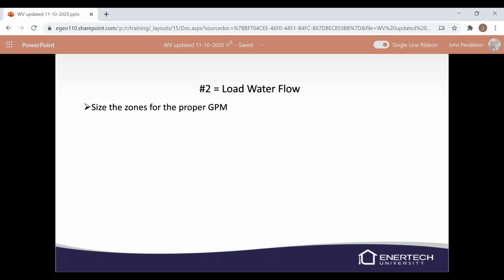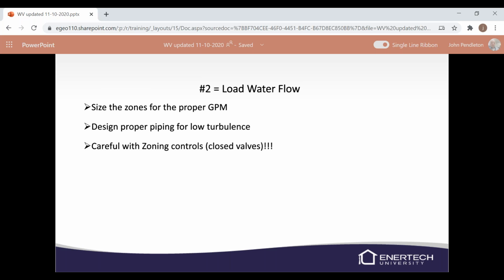And so we may need to look at installing your hydraulic separators, your buffer tank, things like that. Low turbulent piping, be careful with closed valves, deadheading the pumps. It's not good when we deadhead pumps, so make sure you're installing the bypass valve in your zone piping. Always verify your minimum pump speeds. If it's set too low, then it will lock out on water flow. So, I know you probably heard me say water flow about 500 times today, but that's the normal problem we have with the unit. And we've tried to address as many of those issues as possible, but we can't be out there with you when you set it up. So make sure you're setting your minimum pump speeds properly and your bypass valves.